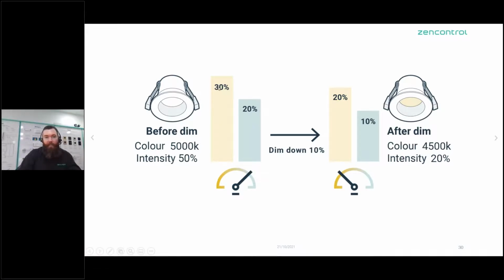If you say had the lights at 30% and 20%, which gave you a color of 5,000 K, an intensity of 50%, because obviously we're mixing these 2 colors. I have assumed 6,000 and 3,000 in my calculations here. Then we press the dim down button a bunch of times to dim down 10%. Well, after that 10% dim, we've seen not only have we overshot our intensity because we've dropped both of them by 10%, but we've also got a color shift, okay? So it's not the same color before and after.